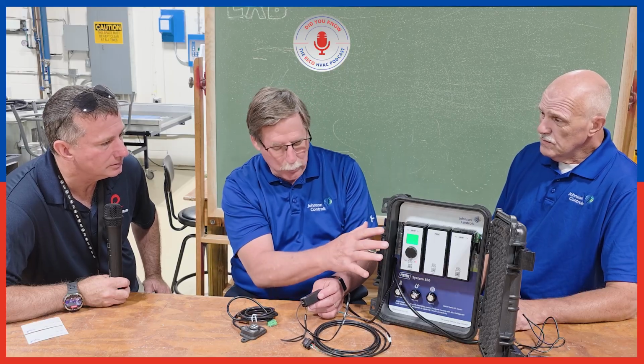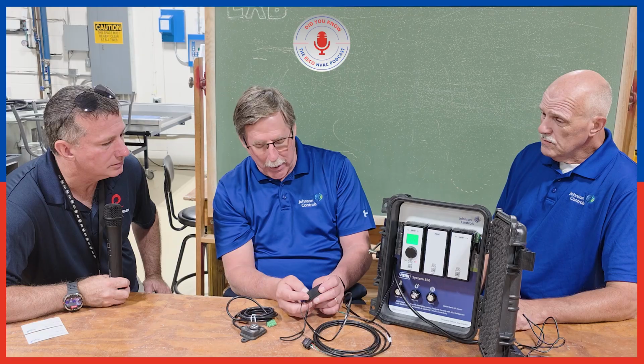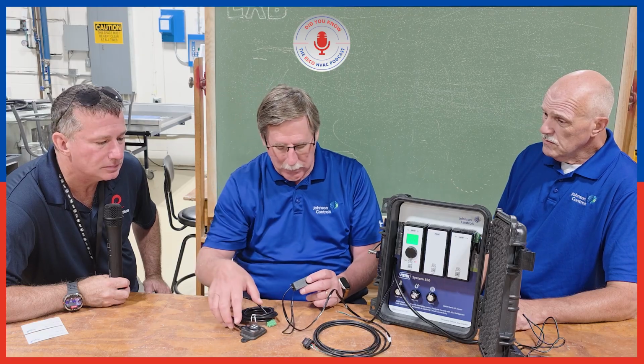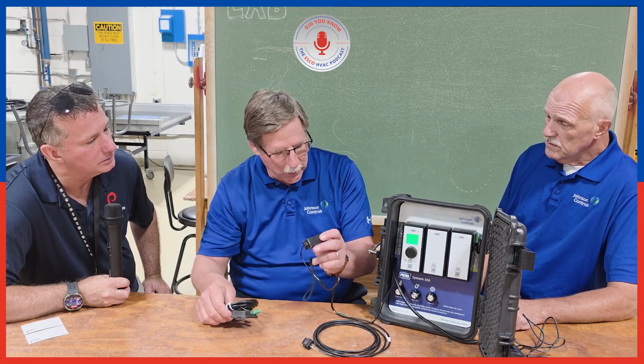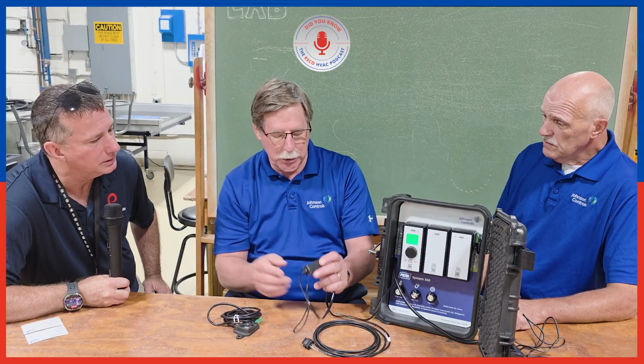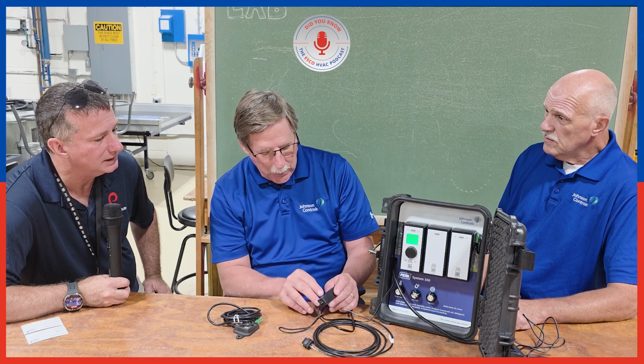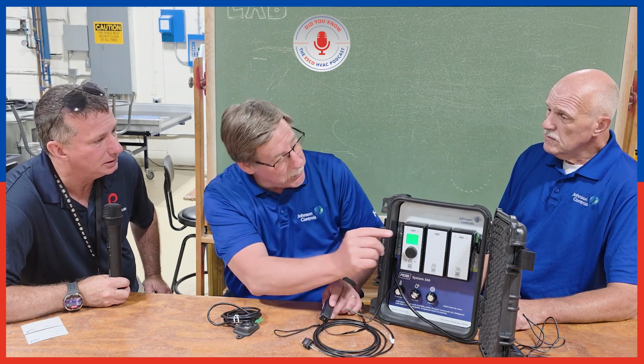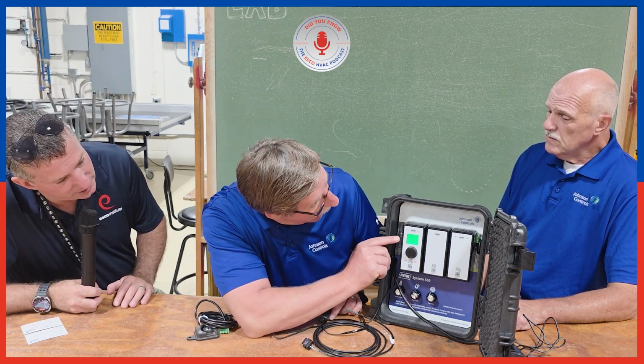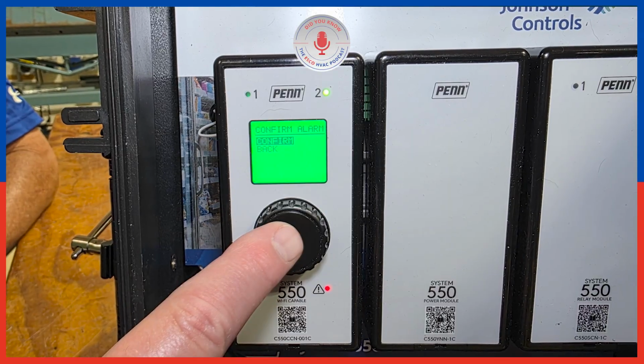You can see here that this gas type is R454A, what we looked at earlier. So it matches what's configured here. Right now, if I had a sensor hooked up to this, which I'm doing through the simulation, it says there's no leak present. But now I can introduce a leak percentage, say 10%, and you'll see immediately that it comes up and says I'm warning now at 10%.